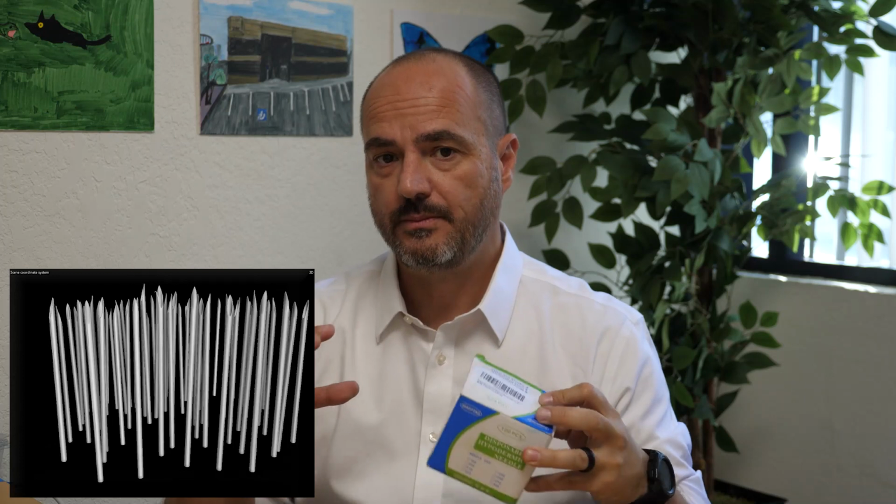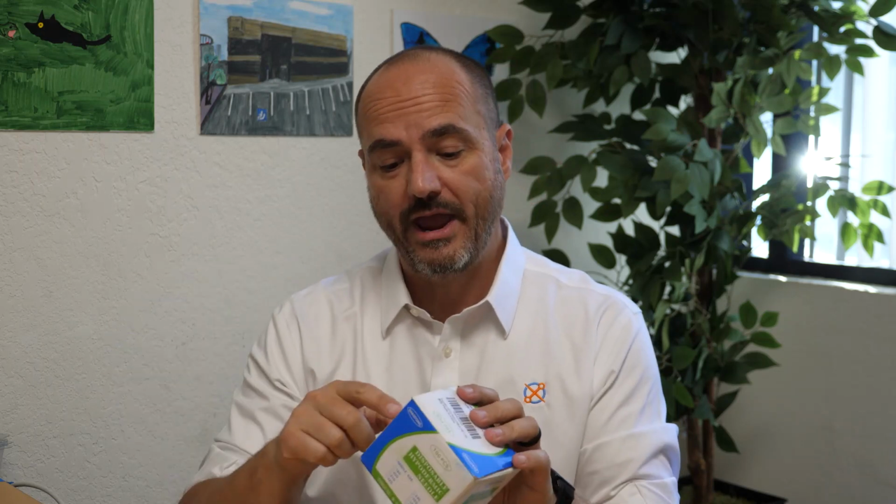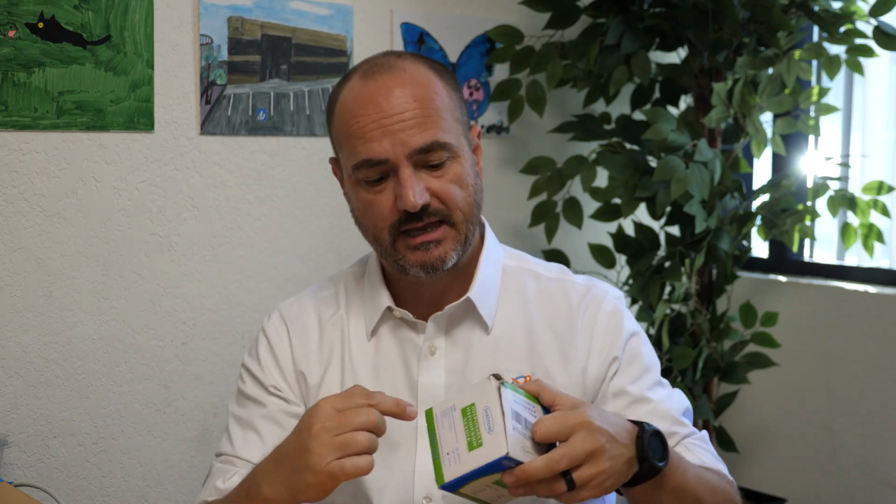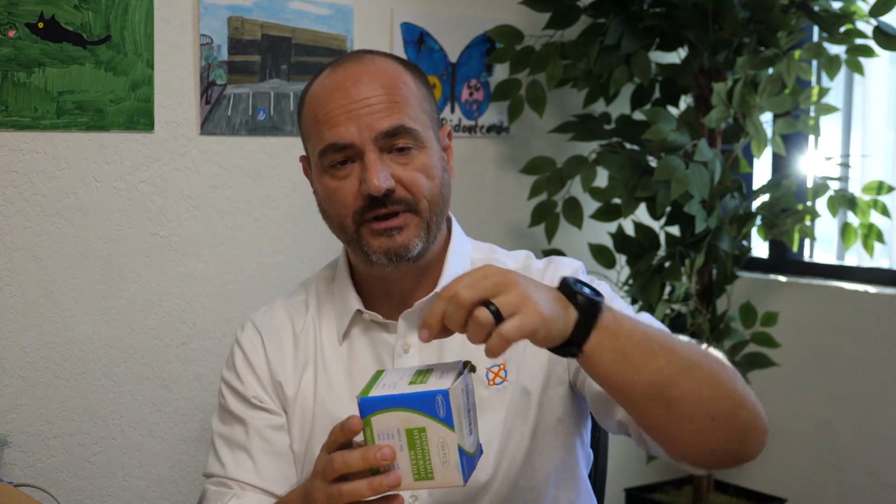So what we did is we did a quick CT of this whole box and then isolated each needle from the CT volume, and then we ran each one of those needles through a computer vision program that calculated the bend of each one of the needles, and based on that, we're able to pass or fail that specific needle. Then knowing where that needle was within the box, we can even, at the next step, open and remove the needle that's not passing quality control.